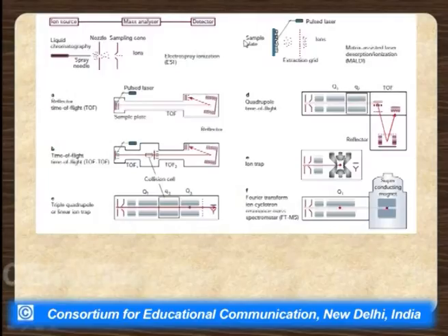Definitely the ion traps and FT ICR techniques are now the newest ones, but routinely most used, cheap in terms of cost of running, purchase and instrument cost, are the time of flight and quadrupole mass analyzers. So, these are the four types of analyzers, and we can see the mass analyzer is the center, the heart of the technique.